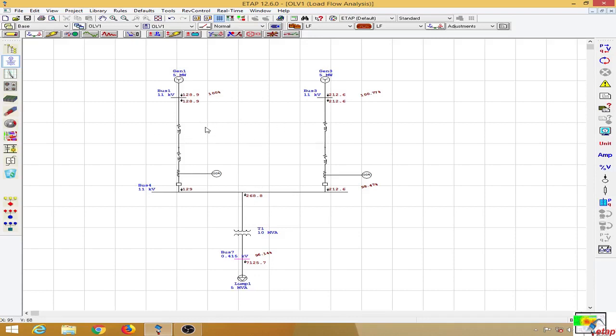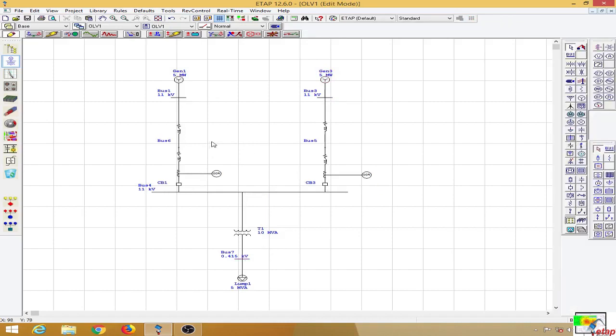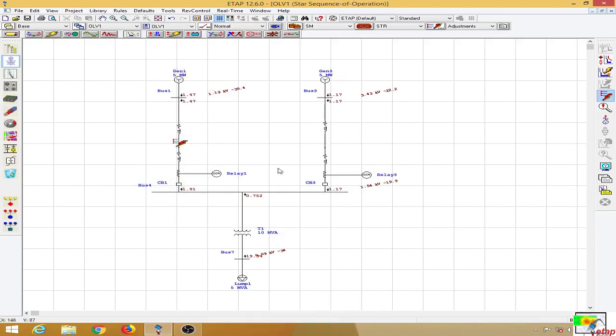When a fault occurs on any of these lines — say at the midpoint between the two lines — Generator 1 will feed to the fault through its line, while Generator 2 will feed to the fault with current flowing through its line, through the bus, and to the fault. I will show the simulation: both relays operate, but we only need to isolate this one portion.